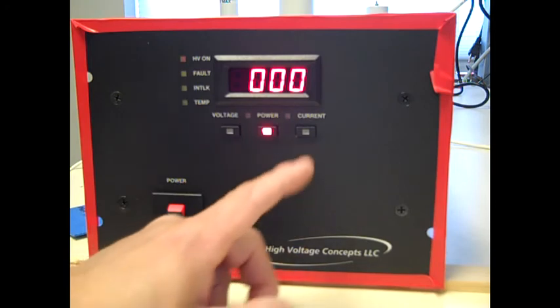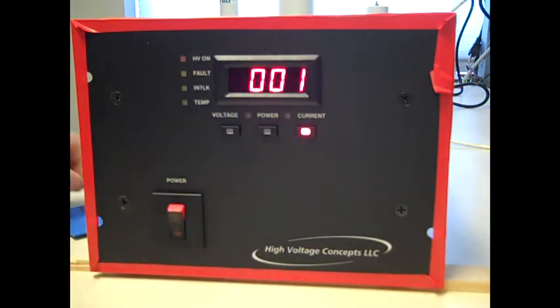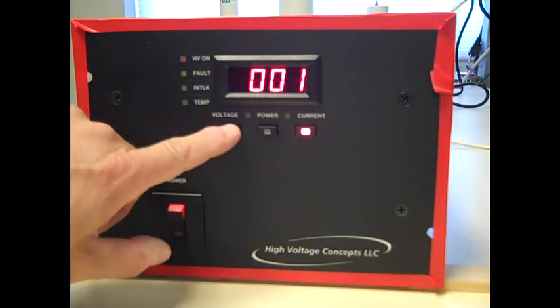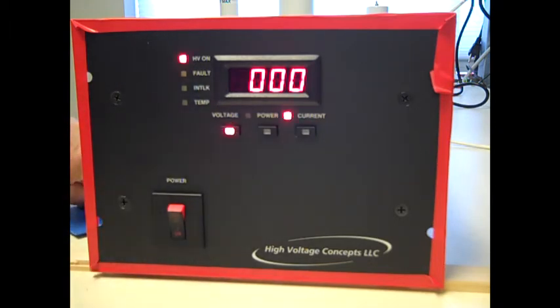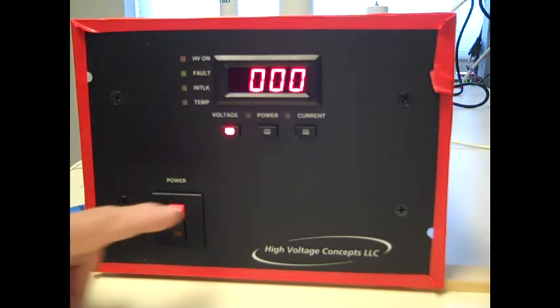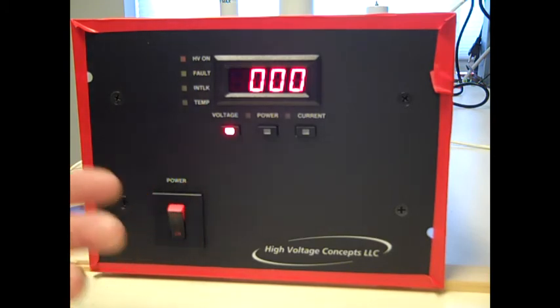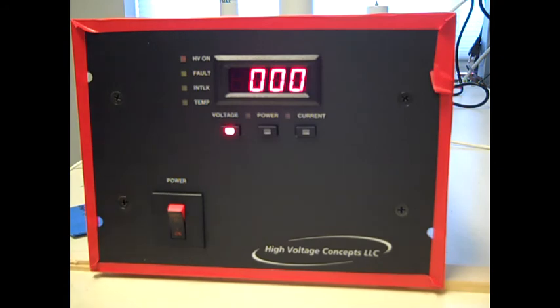Now, why did the power read 0? Let's look at the current while we do that. Put on the current meter, turn high voltage on to the dead short, and we see that it tries to make current and it can't do it. Alright, so let's look at the voltage under those conditions. We have 0 volts, dead short on the output, so it faults off. And that is to protect the power supply, but also to protect any of your equipment. It'll make an attempt for about a second or two, and then it will say, okay, we have 0 volts and I have full current, there's something wrong.